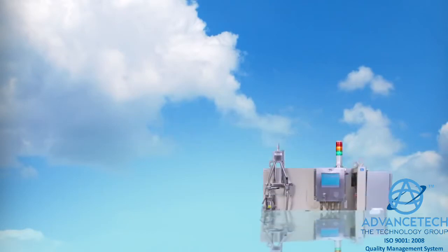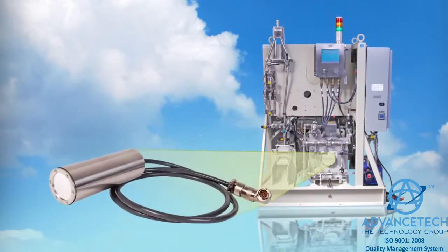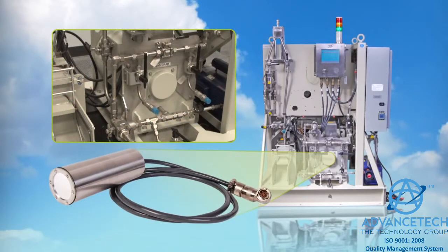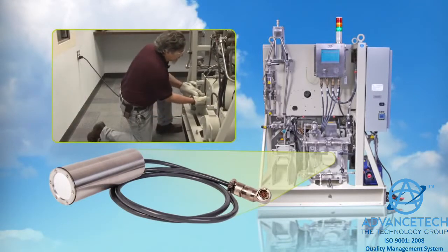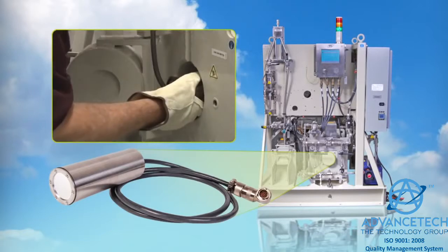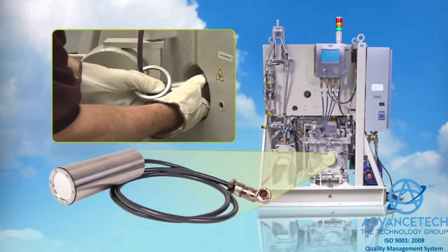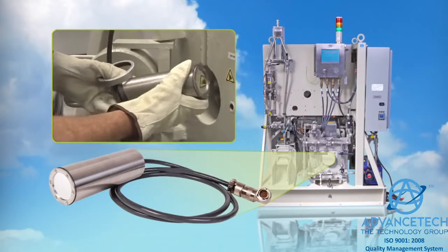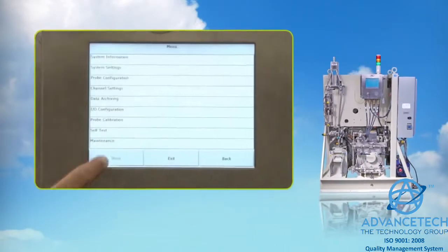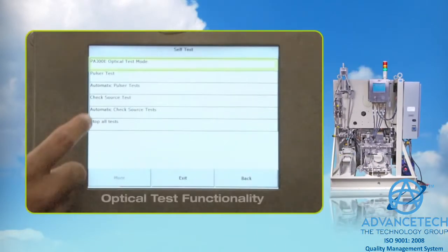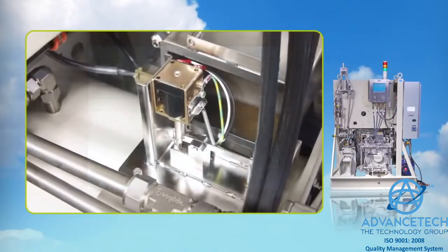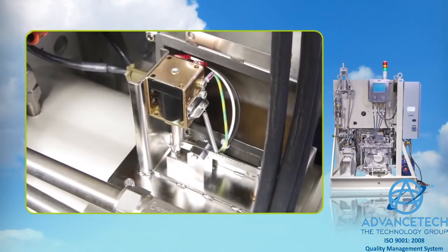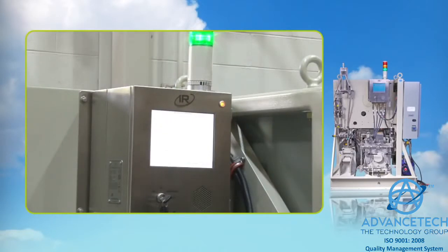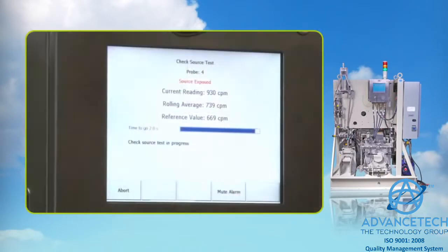The noble gas channel detects beta activity of the noble gas using a beta plastic scintillator detector. As a result, gamma background subtraction is not necessary. The MDN series detectors use LED gain stabilization and also include optical test functionality to verify detector operation without using a radiological source. The system includes a radiological check source. However, that can be operated manually or automatically through the IR7040 rate meter.